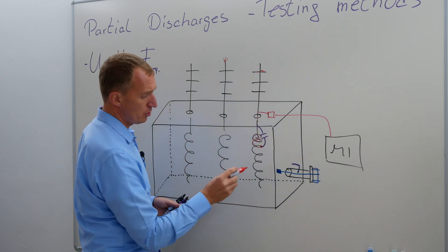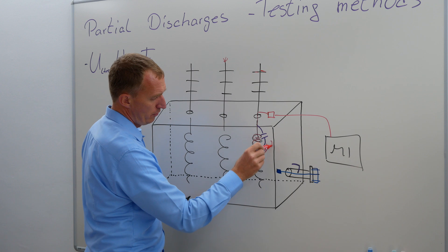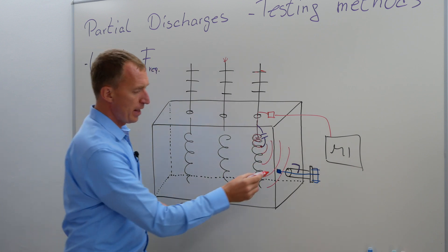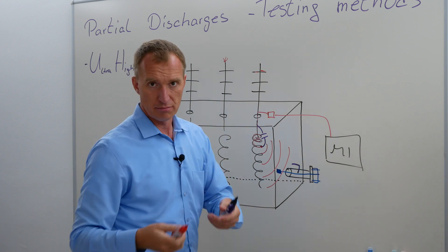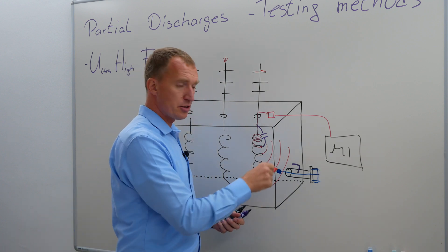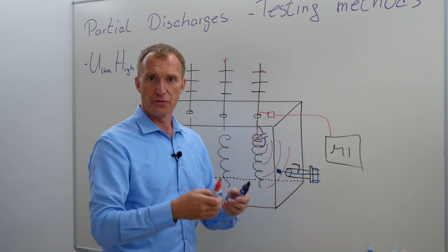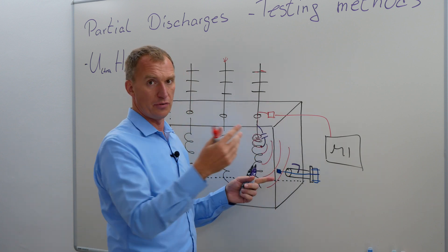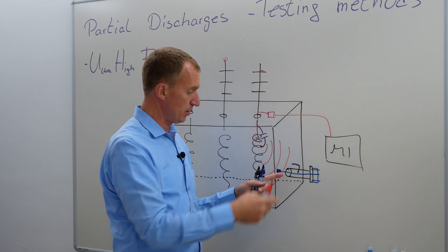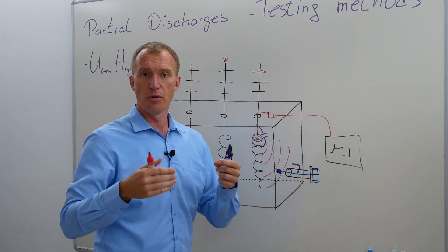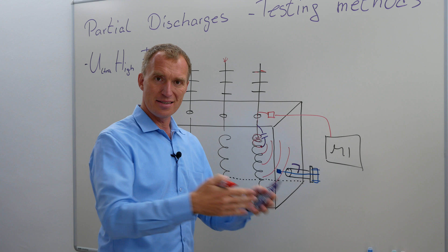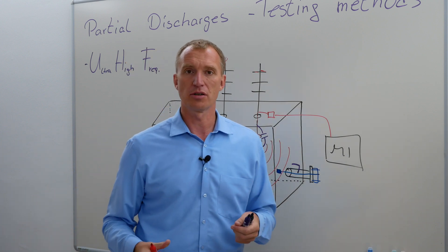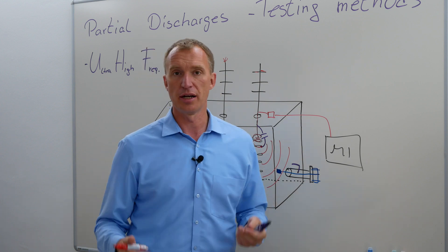However, if I have a partial discharge here, this partial discharge will create an electromagnetic wave, and this sensor can, at least we hope, catch this signal and be able to figure out, whoa, wait a second, there is a certain signal. Very often, if you're lucky, you can correlate it with the electric signal as well. Then you are measuring more or less inside the shielded room, the transformer, you're able to measure partial discharges with UHF.